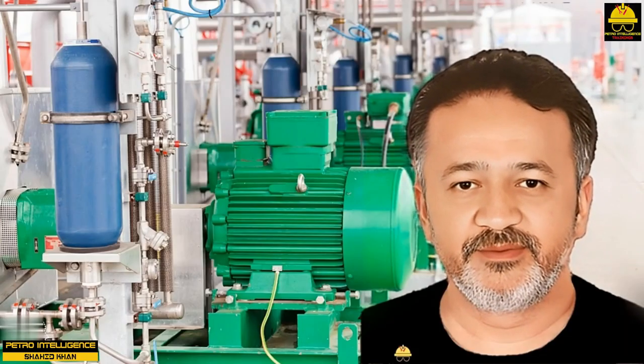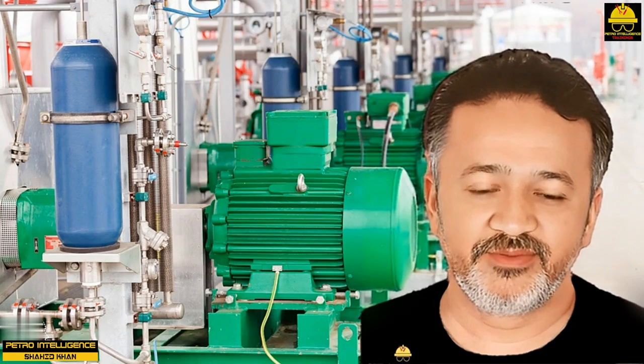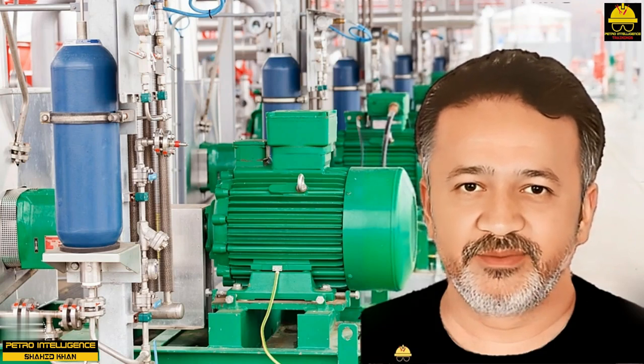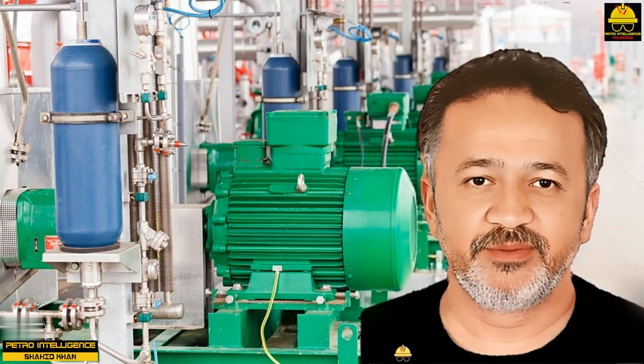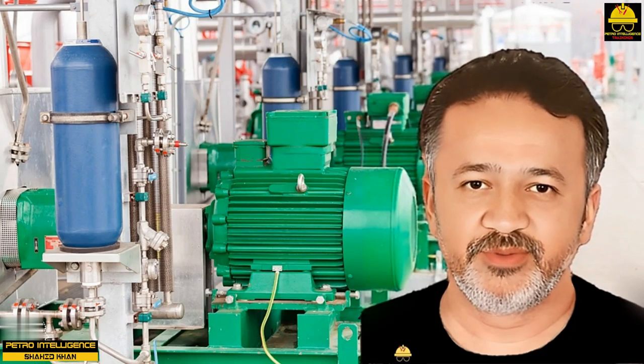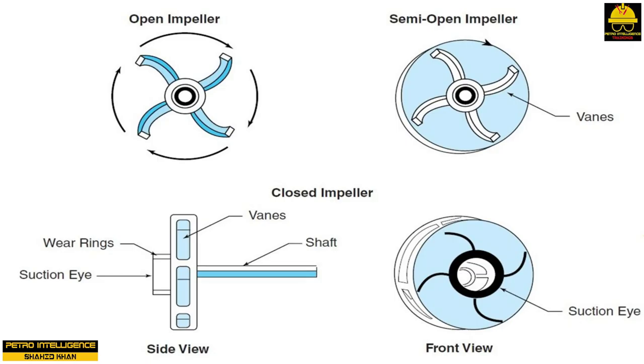Dynamic pumps. Dynamic pumps are classified as centrifugal or axial. Centrifugal pumps operate on the principle of centrifugal force. A spinning impeller inside a shell casing propels liquid outward. Fluid velocity is accelerated inside the shell of the pump and liquid quickly moves toward the discharge port.